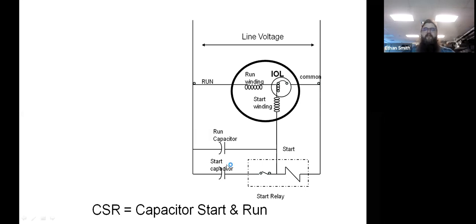It's only rated for use for 1 or 2 seconds. And so when you see these things fail and they don't open up, or you get a compressor that doesn't start spinning and it keeps that start capacitor in circuit, the start capacitor actually overheats, and that's when you get the volcano of goo inside your condenser that came out of the top of that start capacitor.